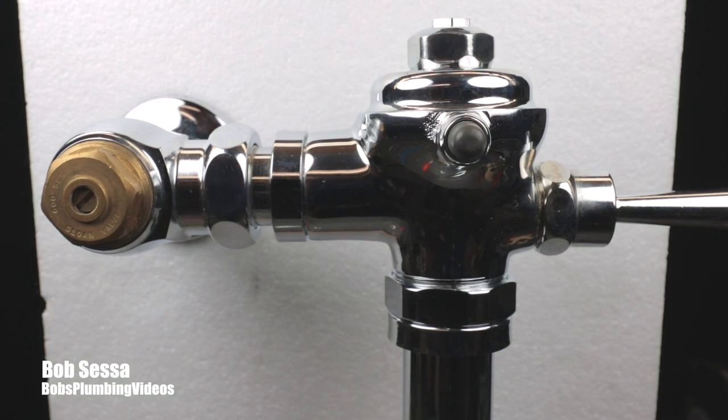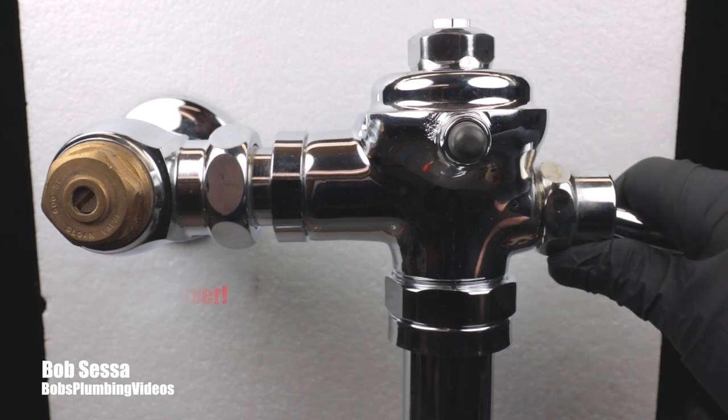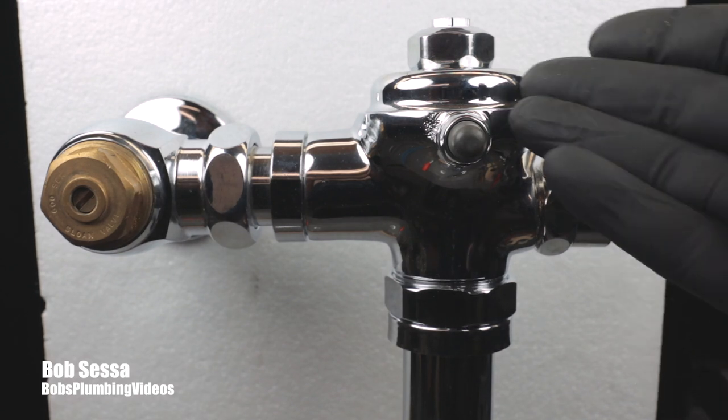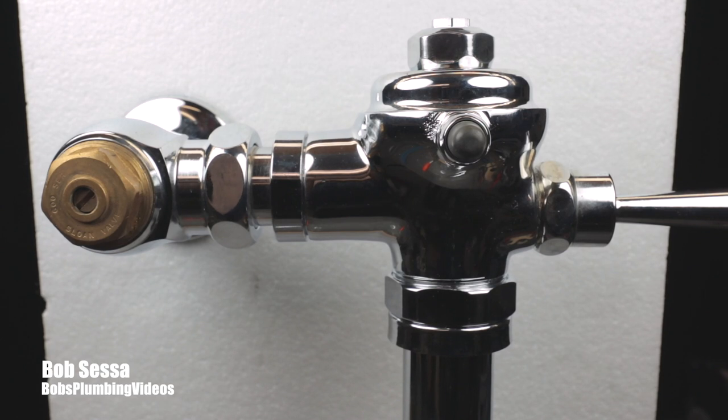And guys, that's pretty much it. If you're experiencing a crazy bang when you hit this handle, let it go, and it bangs like the pipes are going to jump out of the wall — now you know what to do. You've got to replace that diaphragm. And whether it's the Rex valve, a Sloan valve, or a Zurn valve — the Sloan and Zurn valves have rubber diaphragms, this one has a leather diaphragm — they eventually all get compromised.